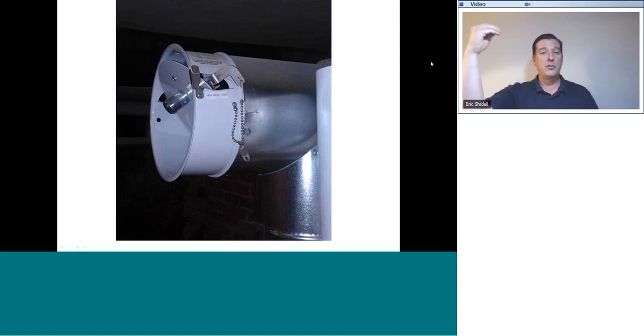This would have several negative effects. First of all, it would pull the combustion products through the appliance too quickly. Therefore, they wouldn't be able to release all of their heat to the air or the water stream, and the appliance would become less efficient. Second of all, it would pull in more air on the burner side of the appliance, messing up the carefully adjusted fuel and air mixture, causing combustion problems.